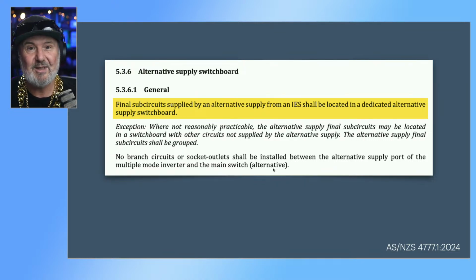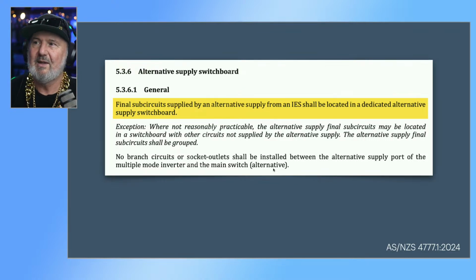But there's an exception. We love our exceptions. Where it's not reasonably practicable, and you can argue that one, the alternative supply final sub-circuit may be located in a switchboard with other circuits not supplied by the alternative supply. The alternative supply final sub-circuits shall be grouped. So effectively, if you've got, let's say, a two-row board, you might have all your grid circuits on the top and your alternative supply on the bottom rail, or you may use space between them, so actually have a segregation and a label to indicate which are live when the grid's not available. So there you go, that's the alternative supply switchboard arrangements.